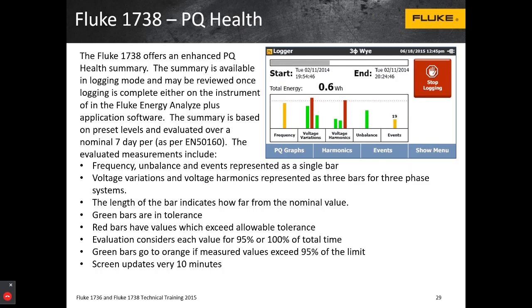So one of the key things is the meter won't automatically set up your voltage for you. It will give you a list of voltages that it thinks you might be using that you can pick from, but you have to select the correct voltage, or you can put in a custom voltage. If you don't set up the voltage correctly, then in the case of the 1736 and 1738, the risk is the voltage events won't be scaled or captured. So you would want to make sure the topology is selected manually.